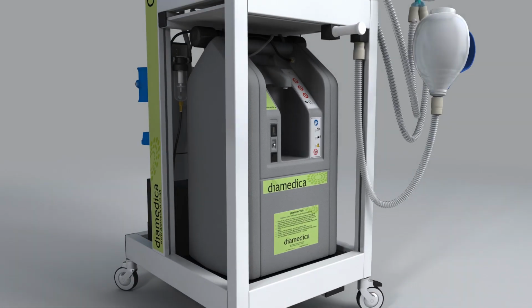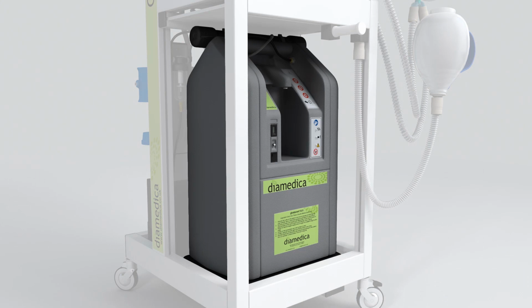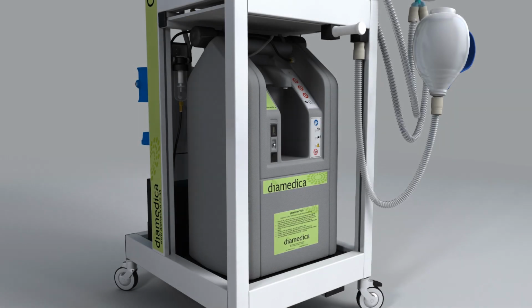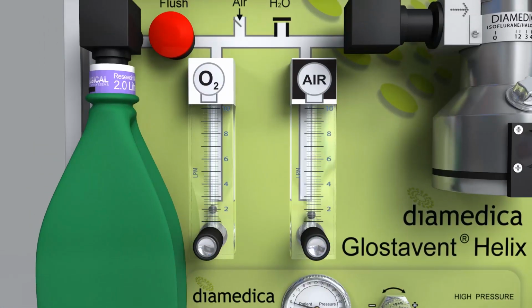The oxygen concentrator will provide oxygen at up to 10 litres per minute at 95%. It also provides air up to 10 litres per minute. There are two flow meters fitted to the Glostavent Helix, one for oxygen and one for air. The flow meters control the amount of oxygen and air supplied to the patient in litres per minute. This is indicated by the float in the flow meter.